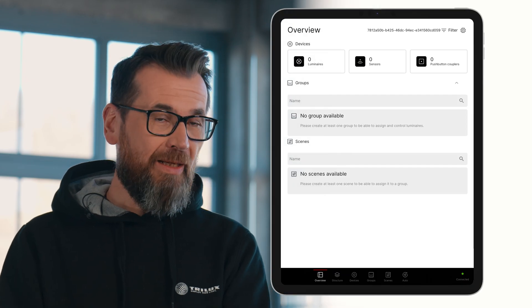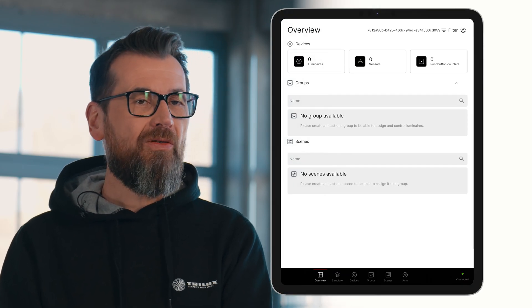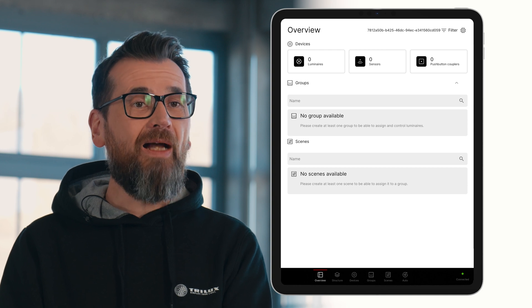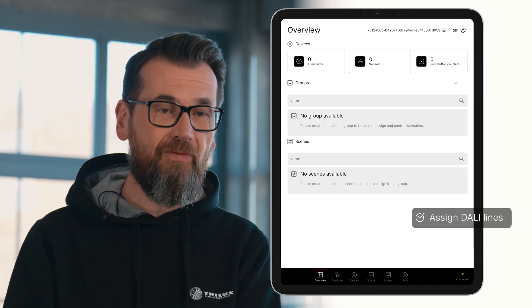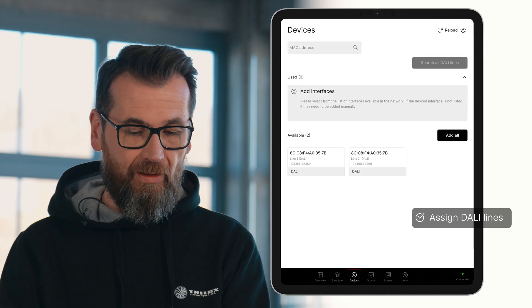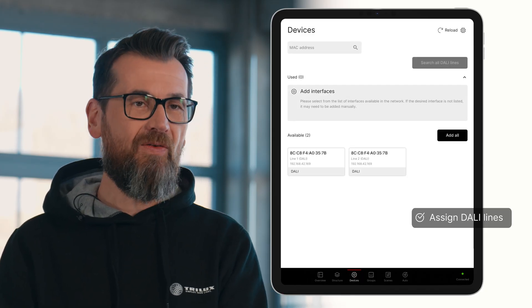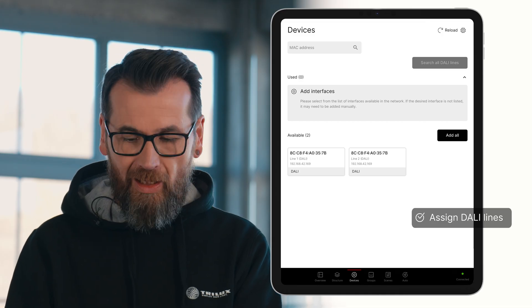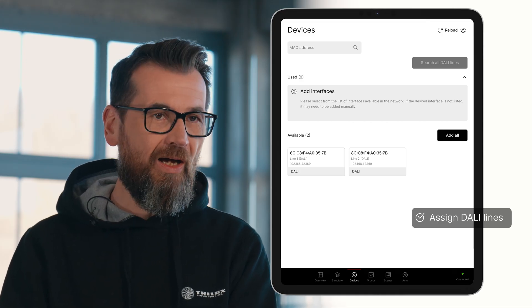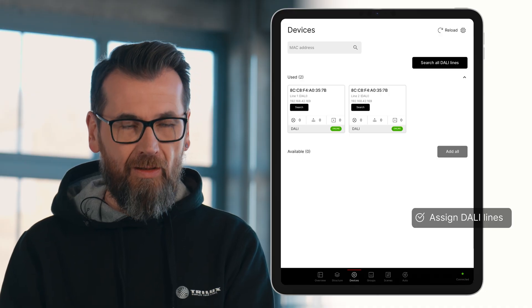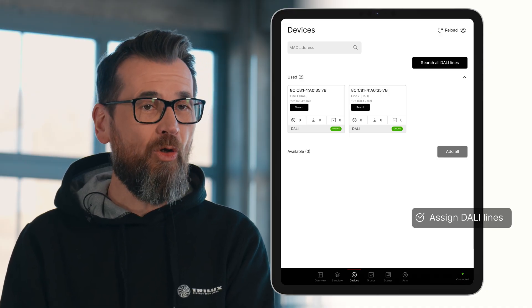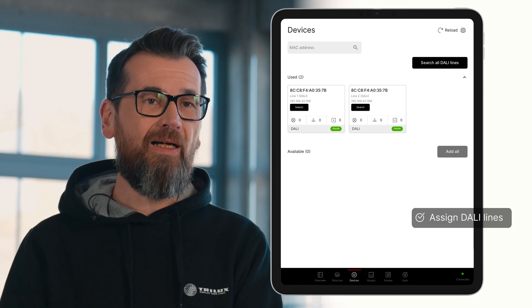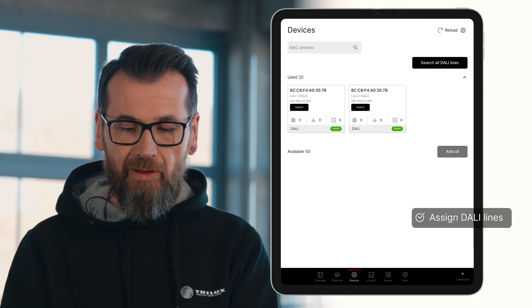We've prepared a Live Link Premium system here to show you, step by step, how to configure it based on a lighting plan. The first step in the Live Link Premium system is to assign the DALI Ethernet gateways — that is, the DALI lines — to the system. To do this, we switch to the Devices menu. In this case, we find two DALI lines that we first need to register with the system. We simply select Add All. Next, we still need to start the DALI search, which means searching for all connected DALI devices, by selecting the option Search all DALI lines.